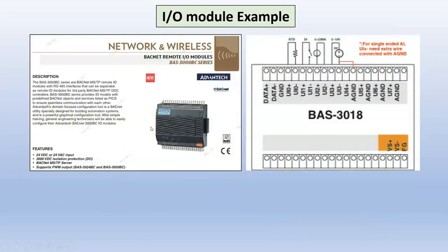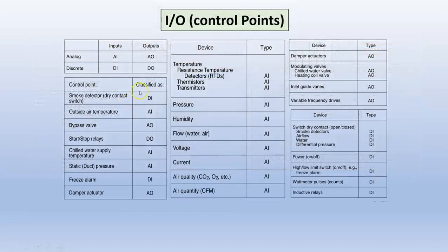Basically, there's 2 kinds of I/O. Let's see, there's 4. There's digital input and output, and there is analog input and output. Analog input typically is 0 to 5 volts, or 0 to 10, or 4 to 20 milliamps, 0 to 10 volts DC. Digital I/O is typically just on or off. You can see here the different types of inputs. Let's see, if you're using a digital input, basically it's going to be a switch of some sort or a relay. It's just 2 states, on or off.